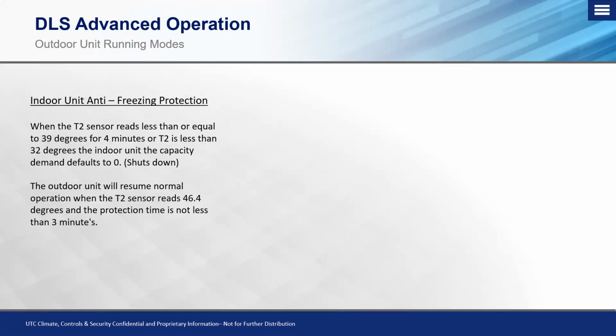So the next one we're going to look at is our indoor coil temperature, which is our T2 sensor. We call this the anti-freezing protection. When that T2, or that indoor coil temperature sensor, reads less than or equal to 39 degrees for a 4-minute period, or T2 is less than 32 degrees, the indoor unit capacity demand defaults to 0, or in layman's terms, it shuts down. Okay.